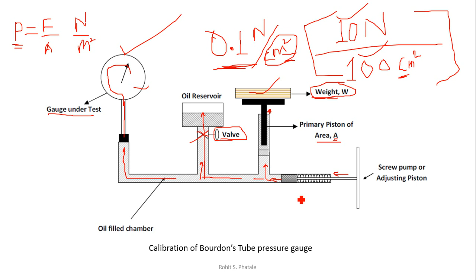Now we will move to the next slide, but before that, if this gauge is not showing the proper reading, if the reading coming out from this calculation differs from the reading on the Bourdon's tube, then we will have to replace parts or calibrate this Bourdon's tube pressure gauge. In calibration we will have to replace some parts that are defective. Sometimes the spring effect of this Bourdon's tube is the main cause of the error.